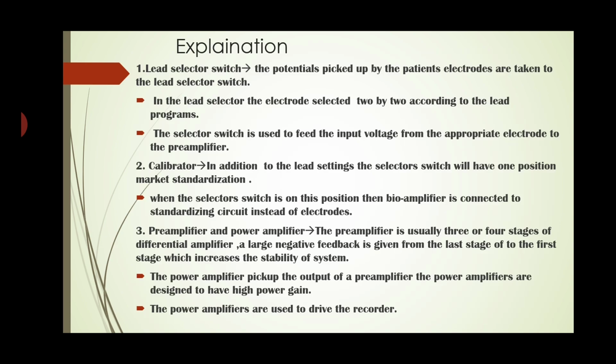Second, calibrator. In addition to the lead settings, the selector switch will have one position marked as standardization. When the selector switch is in this position, the bioamplifier is connected to a standardizing circuit instead of electrodes. So using this calibrator, they are standardizing or checking the working of the amplifier as well as the electrodes, meaning whether it is working properly or not. They are making the calibration of the circuit or electrodes.